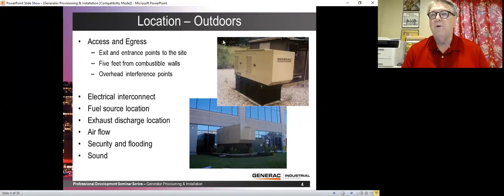Cooling, you want to have proper cooling. This particular generator, both of those in the pictures, show air exhaust going upwards, and that's really the best way to do it. And for Generac, that's pretty much standard in all of their smaller generators.